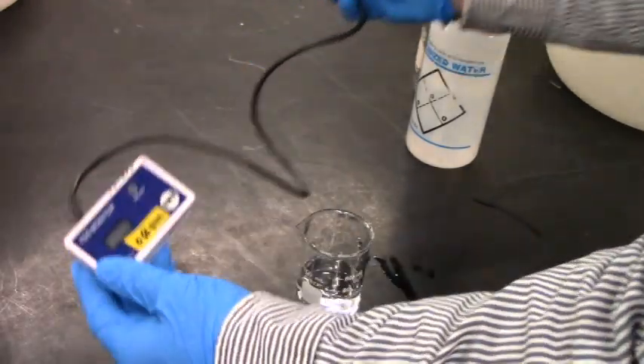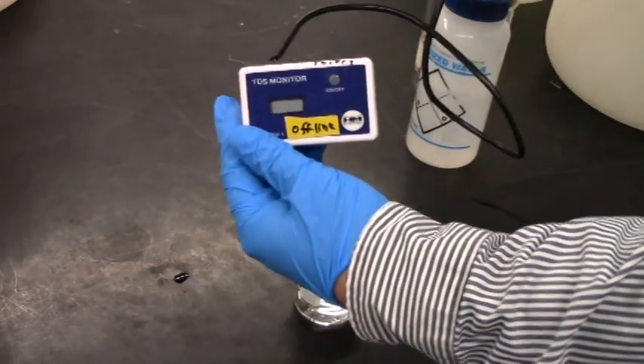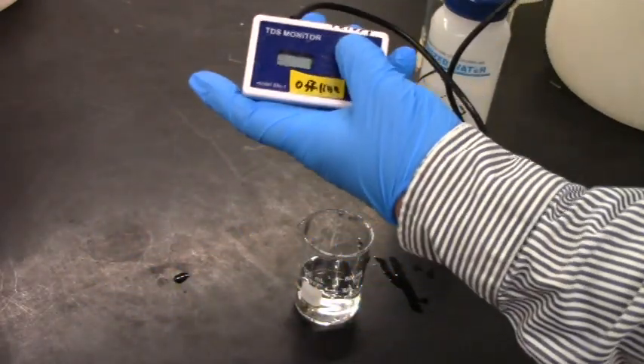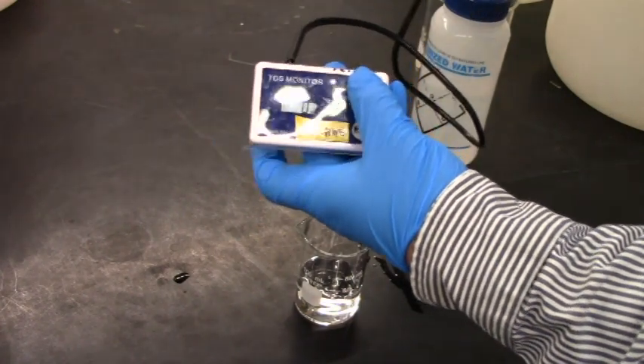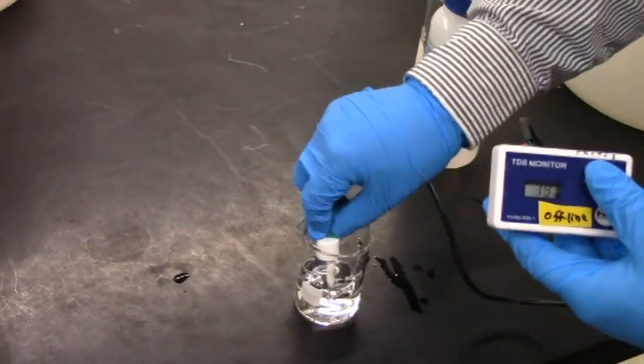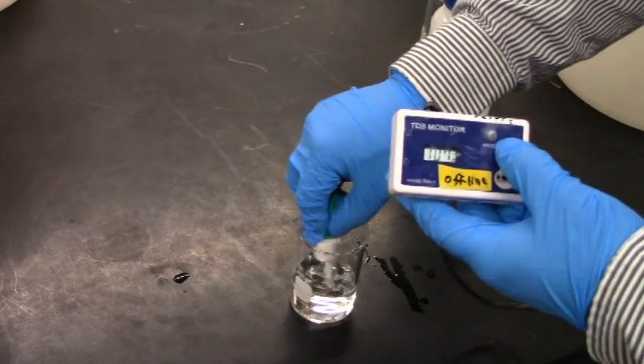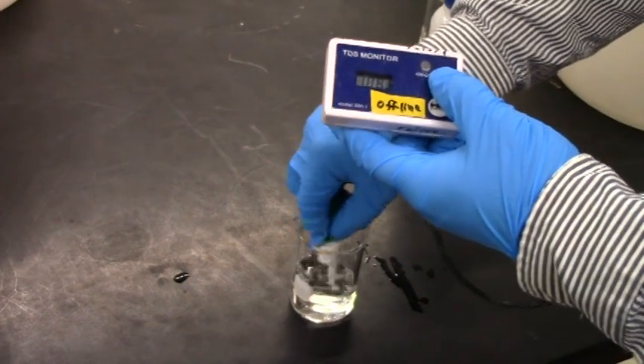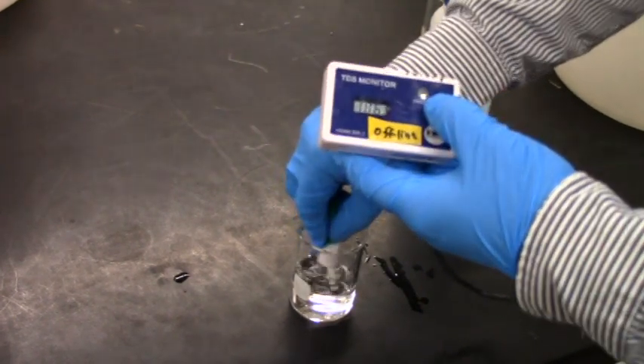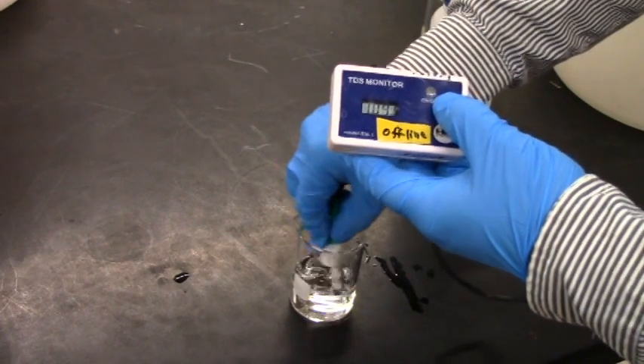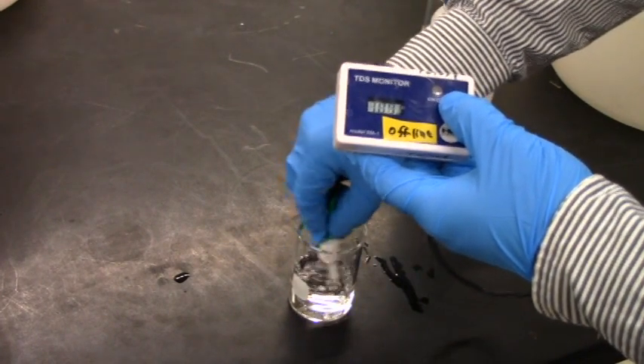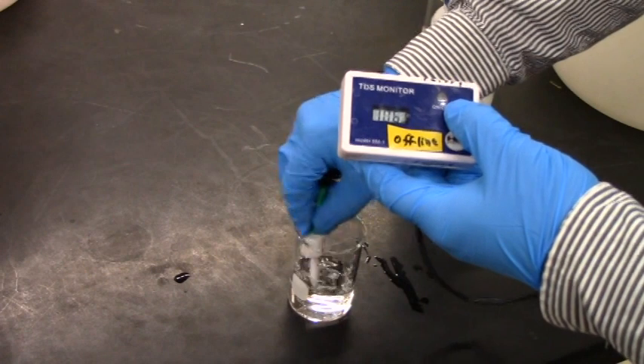Use an offline TDS meter to measure the ppm values of the three samples. Shake the probe a little bit in solution and wait until the reading stabilizes. These values give accurate salt concentration compared with the inline TDS meter.